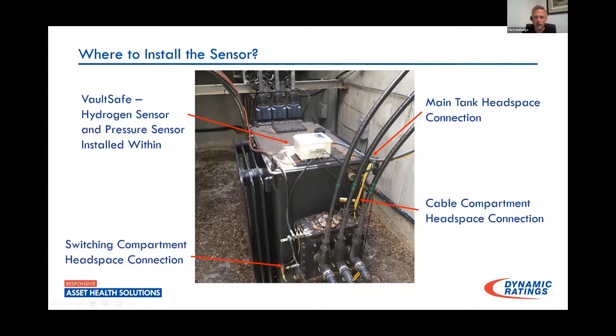Again, we only use the one pressure transducer, and it's actually located within the box. We use a polycarbonate box, it's just more effective against corrosion, especially when we start looking at oxidizing agents, salt solution. The adapters are all silicon bronze, and these adapters go into existing ports in the transformer. So again, you're really not making any modification.